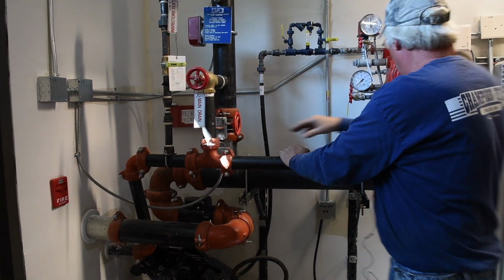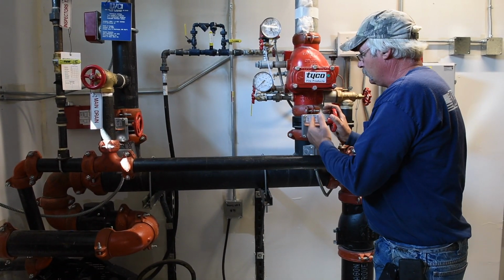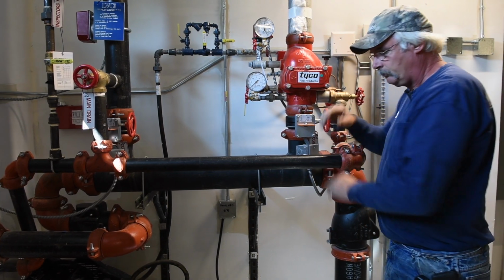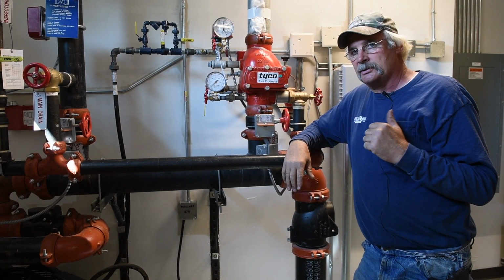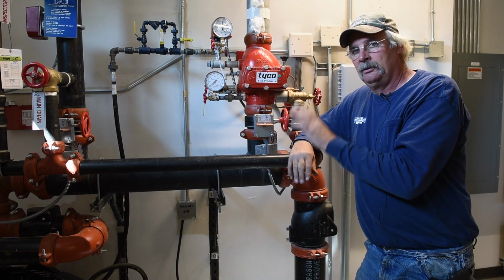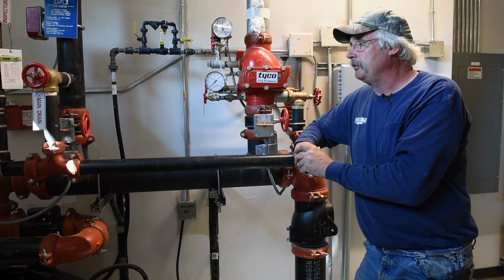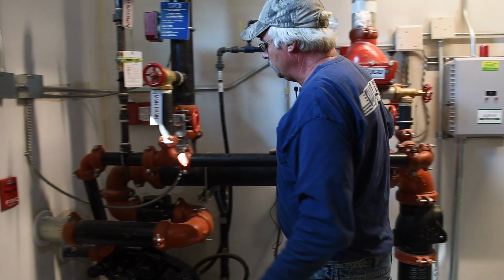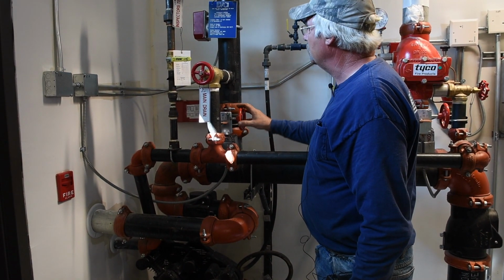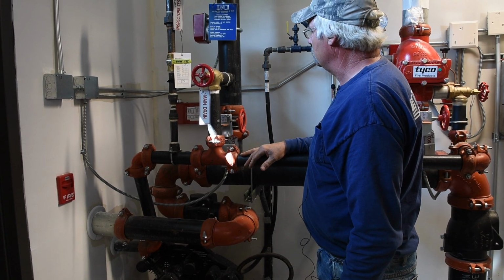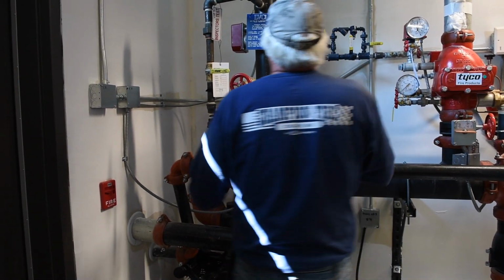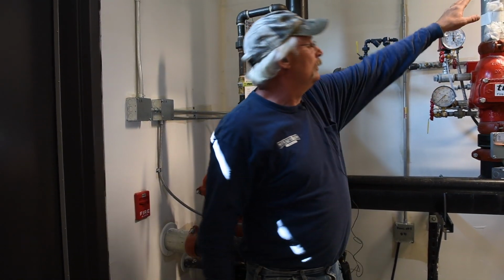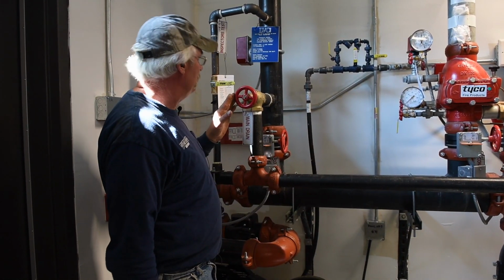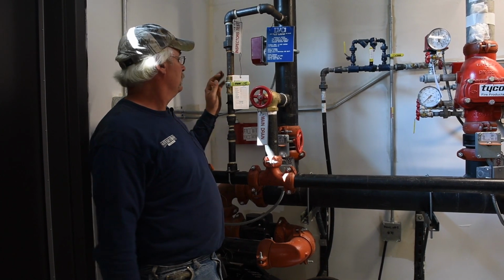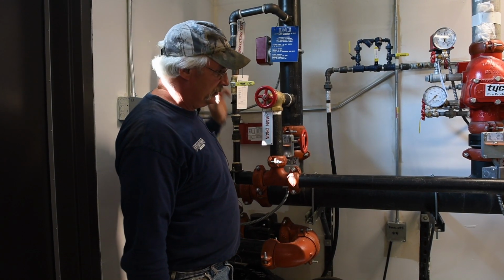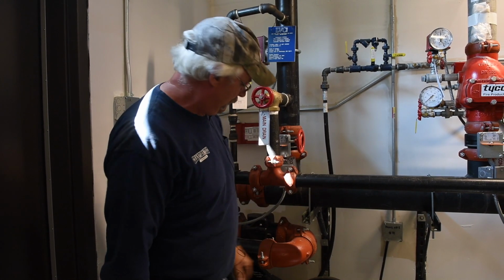Again, these 2 control valves are shut off. These are normally in the vertical position. Right now, the fire alarm panel is picking them up that these 2 control valves on the south mechanical are shut off. The systems are charged and everything. Once this is open, let's say you had an issue with a sprinkler head or anything like that, go right back to the steps. Close control valve A, open main drain B, open inspector's test C. And we've got them all signed, and everything's wet, everything's dry.